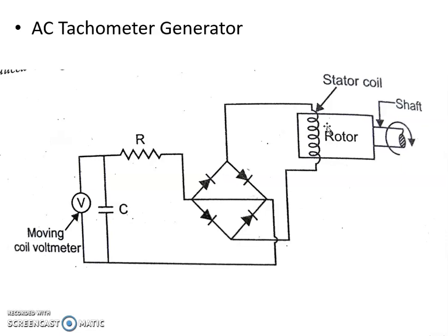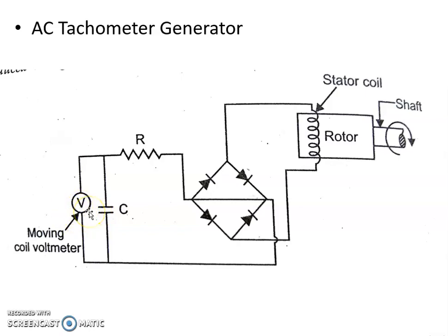The EMF induced in the stationary stator coil is an alternating EMF. The alternating EMF developed across the stator coil is converted into DC voltage by means of a bridge rectifier. The ripple content present in the DC voltage is removed by a capacitor filter, and the converted DC voltage is measured with a moving coil voltmeter. The voltage shown by the voltmeter is directly proportional to the angular velocity of the shaft — as velocity increases, more voltage is induced across the stator coil.